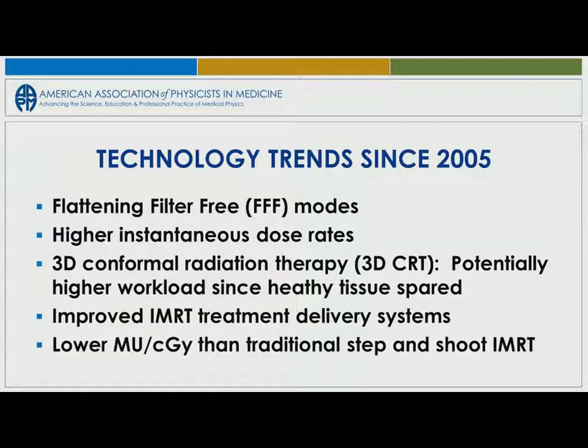That's what's changed since 2005. Nearly all your machines today have flattening filter free modes, so you have your high dose rates, giving you the higher instantaneous dose rate. Everybody has 3D ability, arc therapy. You have potentially higher workloads. Everybody's doing IMRT, and thank heavens we now use a much lower monitor unit per centigray than your traditional step and shoot.